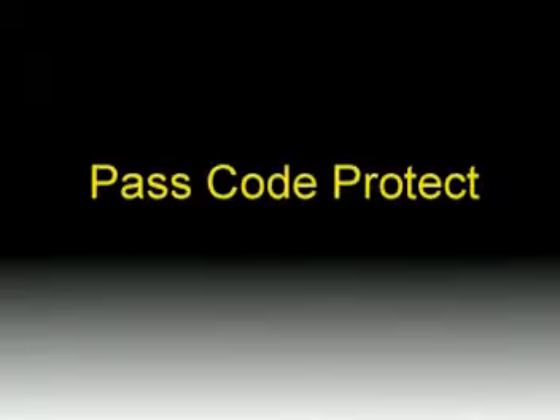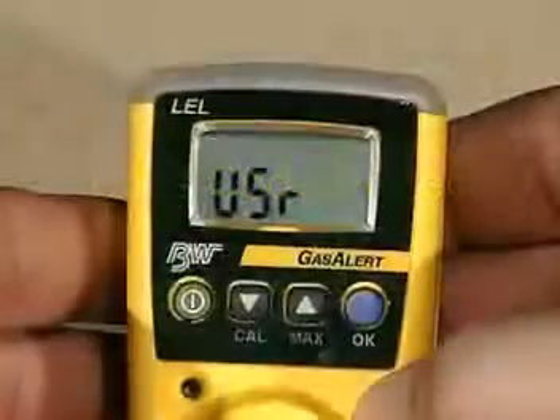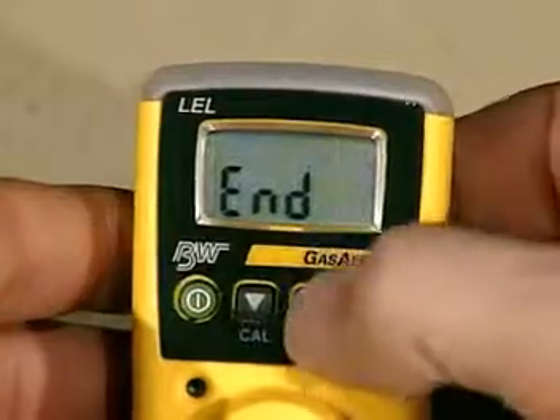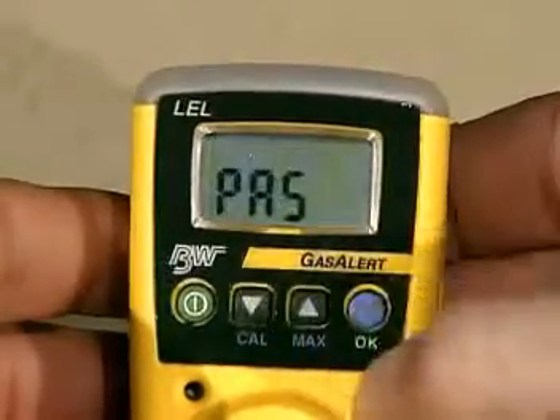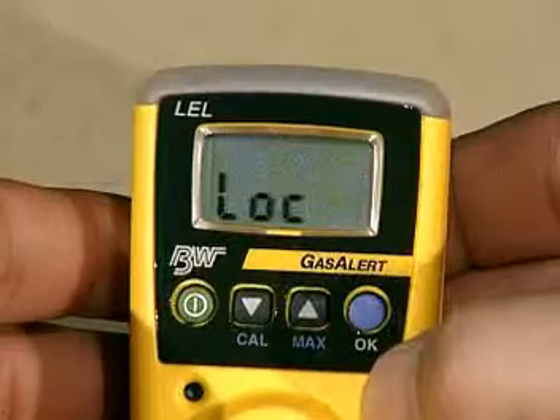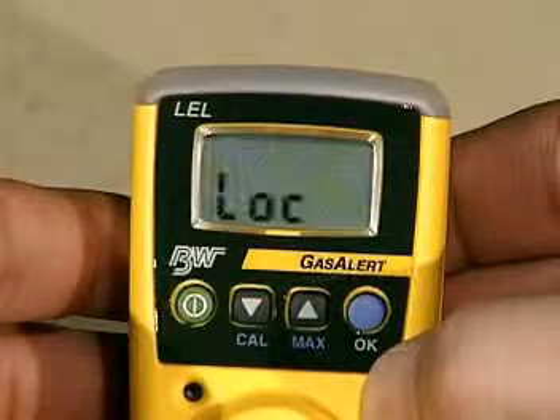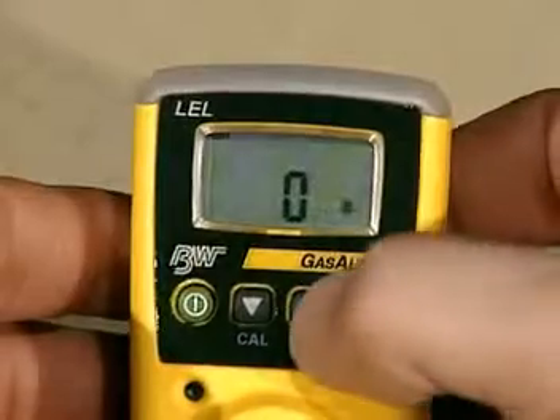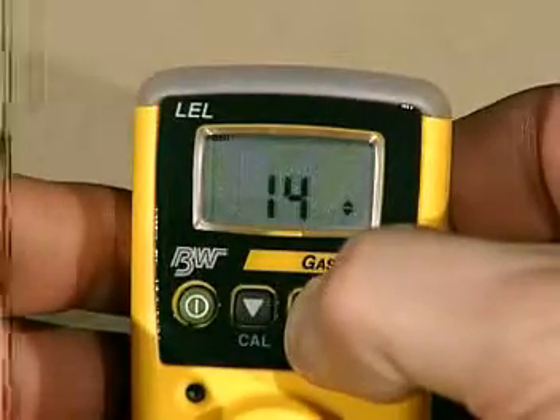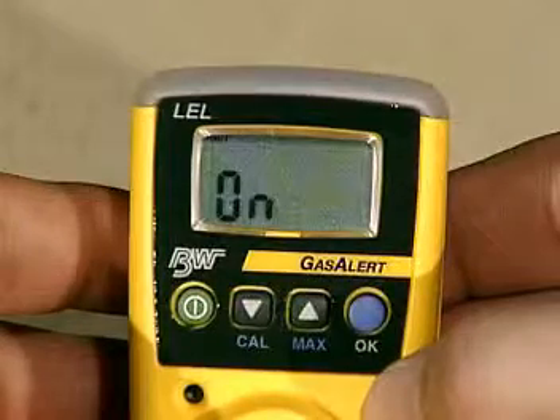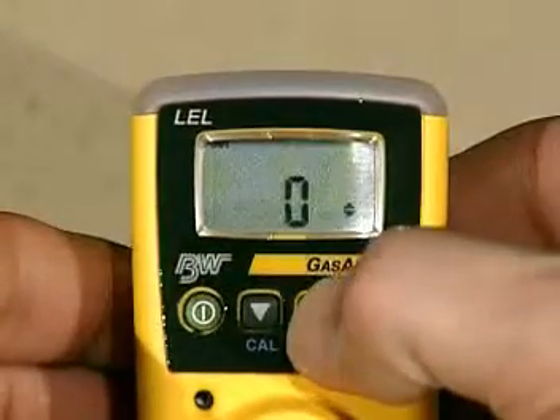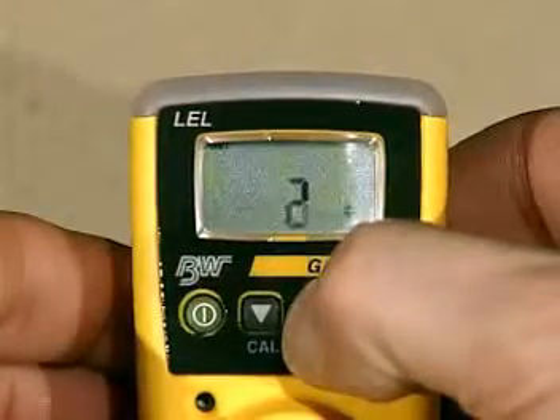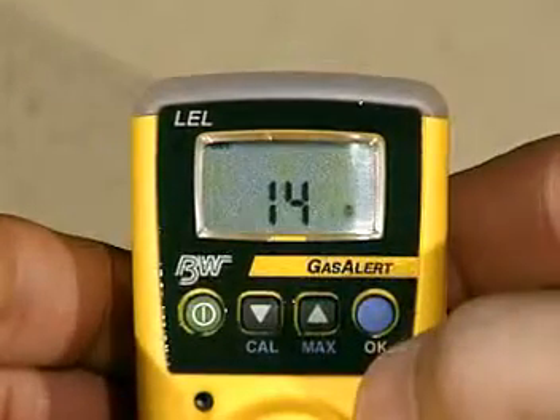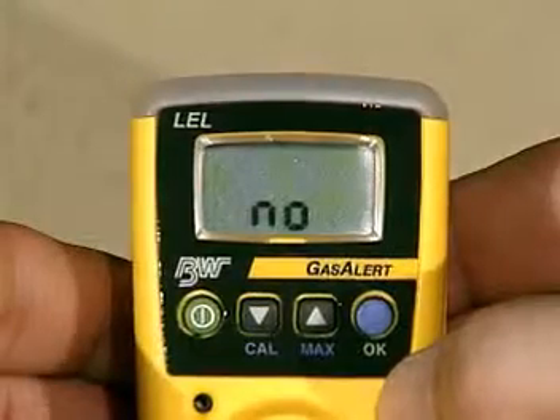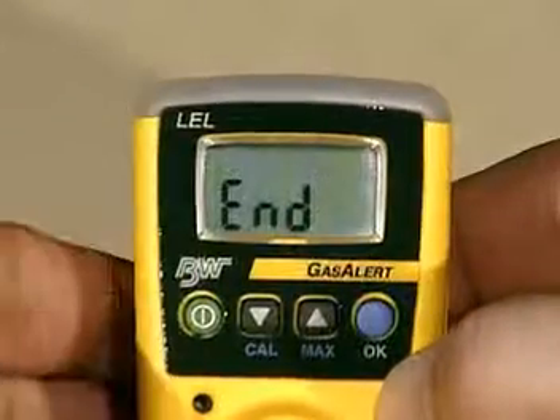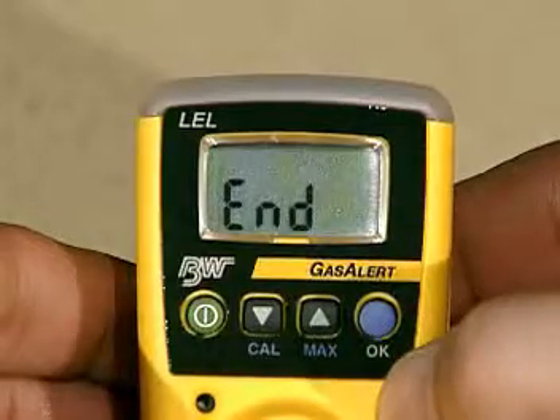Passcode Protect prevents user access to the calibration and alarm functions. To activate or deactivate Passcode Protect, press the OK button when the screen reads Pass Lock. Enter the factory passcode using the up-down arrow keys. When activated, the screen will read On. If an incorrect passcode is entered, the display will read No, and the detector will beep 4 times and return to normal operation. Select End at any time to exit the User Options menu.